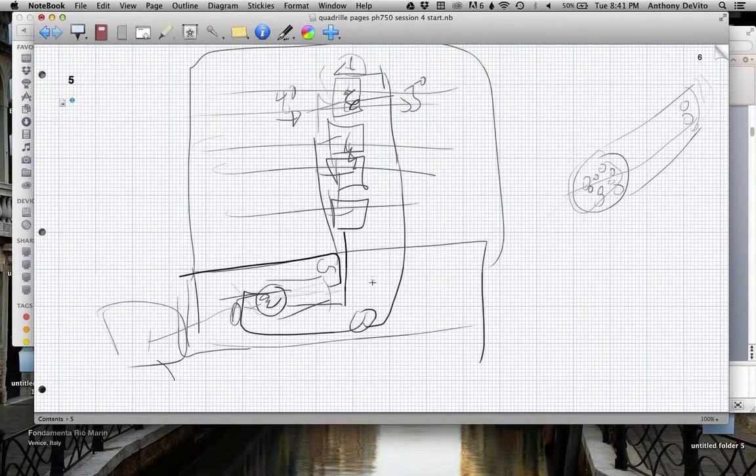So instead of doing that, they take that Freon and send it into another similar shell with tubes in it. That's called a condenser. This is called a water-cooled condenser, and you do exactly the same thing. There's a compressor that compresses the gases. Very frequently, that's either a centrifugal device or a piston-driven device, usually electric, but it can use other sources of energy. You compress it into a hot gas, and the hot gas gets released into this water-cooled condenser.